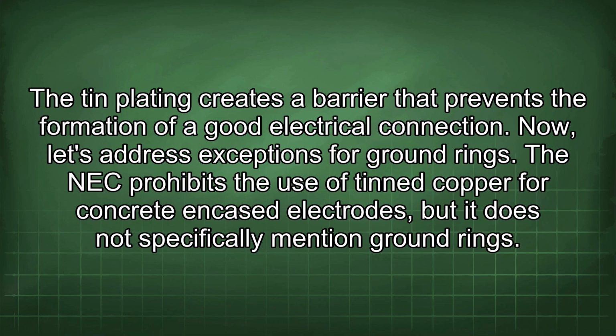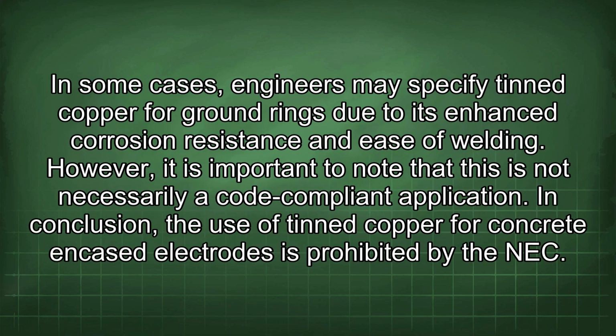Now let's address exceptions for ground rings. The NEC prohibits the use of tinned copper for concrete encased electrodes, but it does not specifically mention ground rings. In some cases, engineers may specify tinned copper for ground rings due to its enhanced corrosion resistance and ease of welding. However, it is important to note that this is not necessarily a code-compliant application.